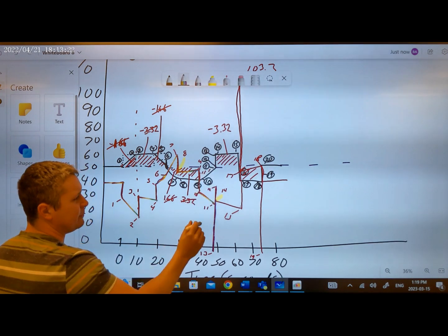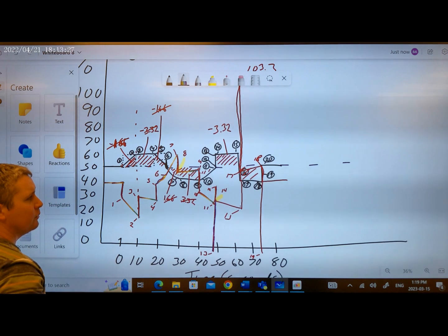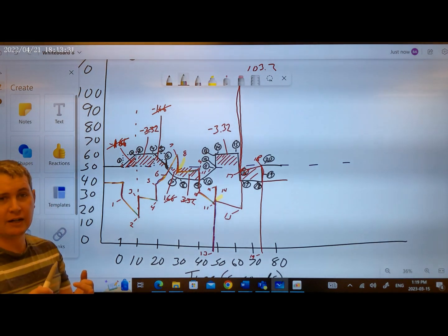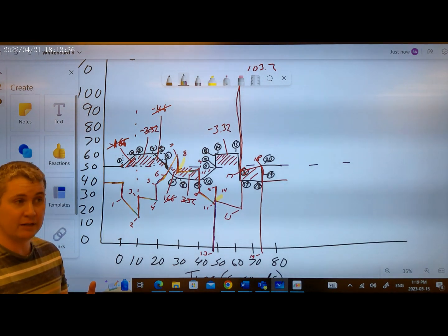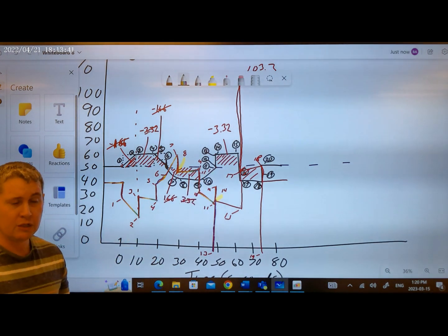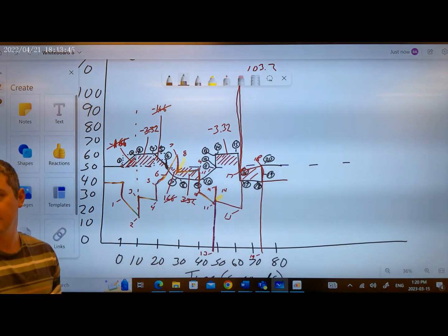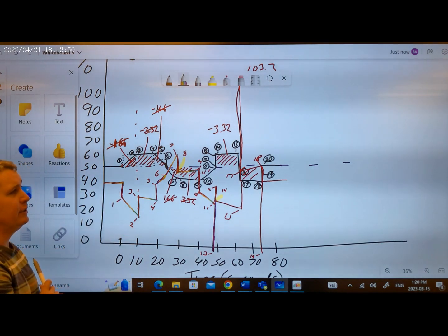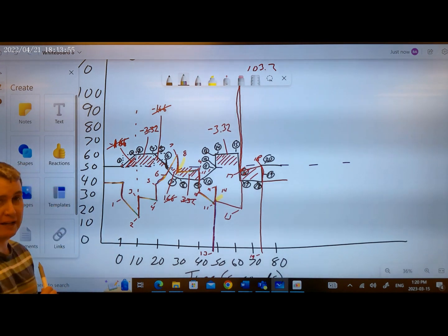But then as soon as that ramp stops, we jump up because we no longer have a ramp rate. So we don't have derivative, we don't have any new integral or accumulated old integral. And because we have a 0 error, we don't have any proportional. So we were left with the bias of 50, our starting point, which makes sense. Because we started off at 50, and our set point was 50.